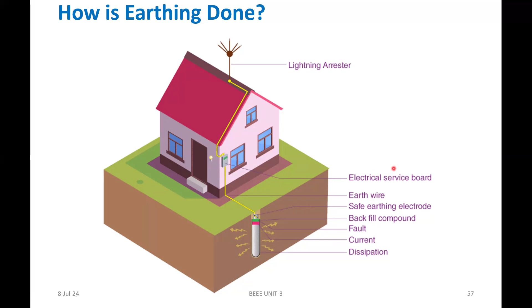And we have to learn how we can make this earthing. There are three types of earthing: pipe earthing, plate earthing, and strip or rod earthing. The first one is pipe earthing. Pipe earthing is the best and most efficient way of earthing, and it is also affordable. Pipe earthing uses a pipe of 30 mm to 38 mm diameter and 2 meters length, vertically embedded into the ground to work as an earth electrode.